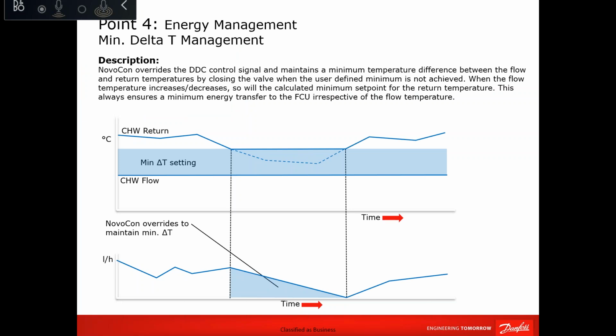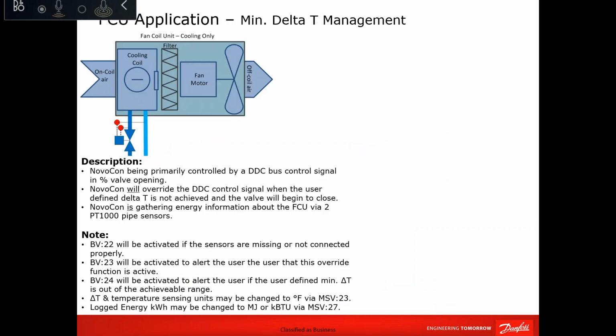So the second feature which you can enable, the first one being the power control, is minimum delta T management. Minimum delta T management works in the same way. It will maintain a minimum temperature difference. The meaning of that is, when the delta T that you set in the Novocon, as measured by the temperature sensor, is less than the set point, the Novocon will start to close. And it will keep closing until the delta T is back to your set value. Once it is back to your set value, the delta T management will be disabled and it goes back to the same scenario.